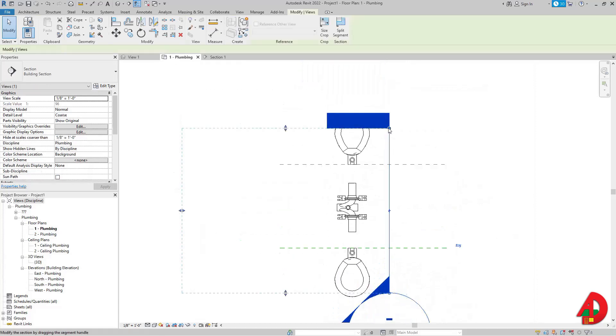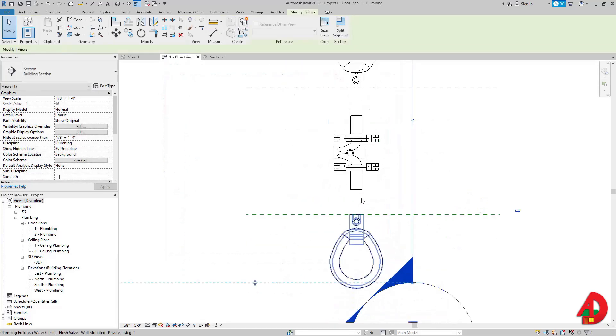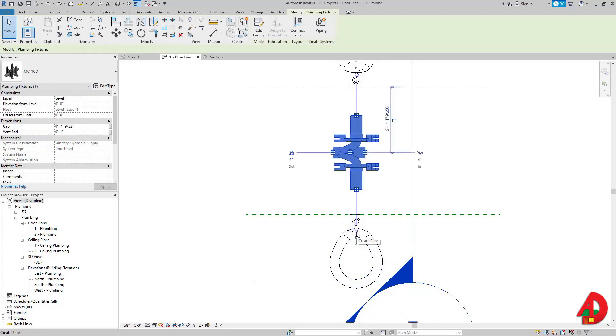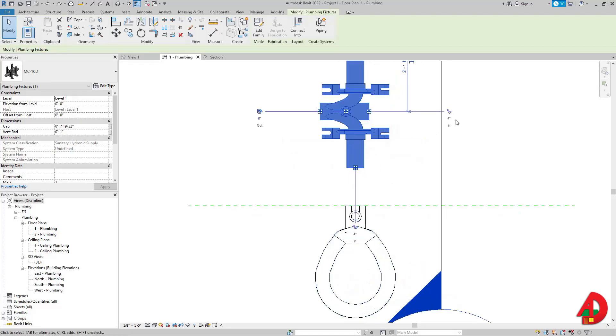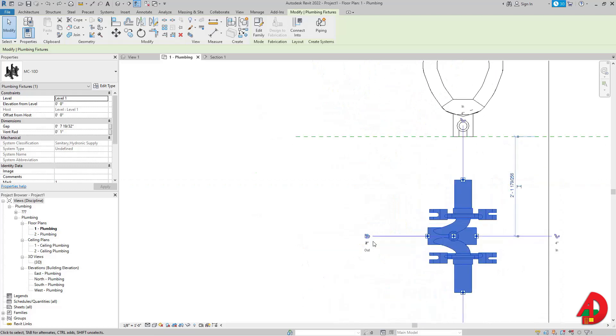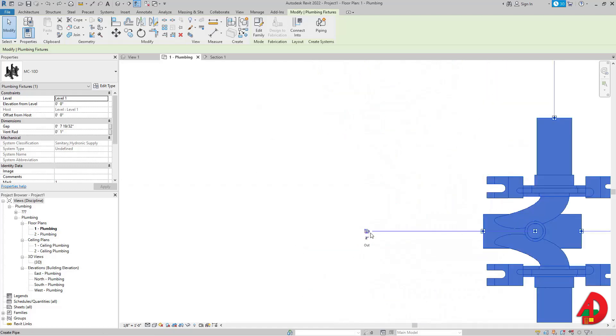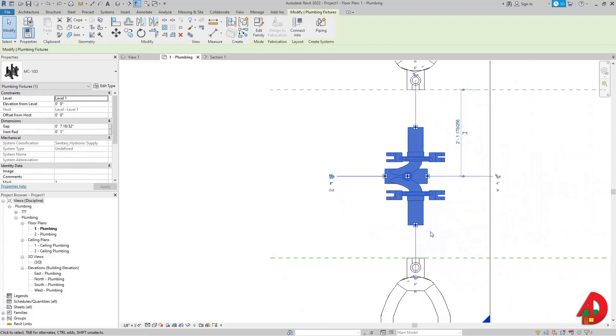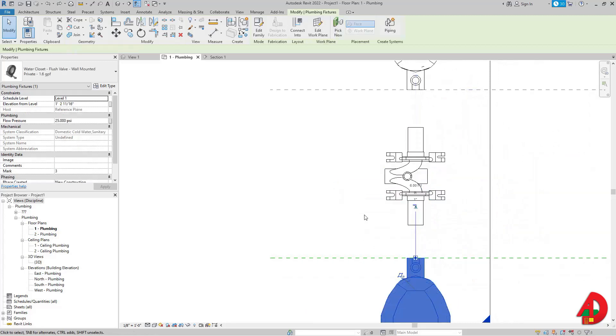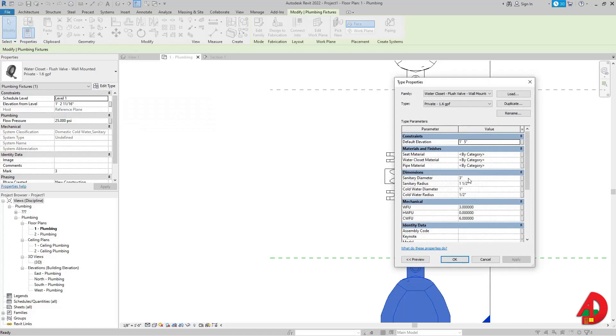Back in the plumbing view, this carrier has a diameter of four inches — four inches in, four inches in, and four inches out. We can see the vent diameter and sanitary diameter. Since the carrier has a four-inch diameter, the water closet should also be four inches. I'll select one, go to Edit Type, set the sanitary diameter to four inches, set the waste fixture units to four, press Apply, and OK.